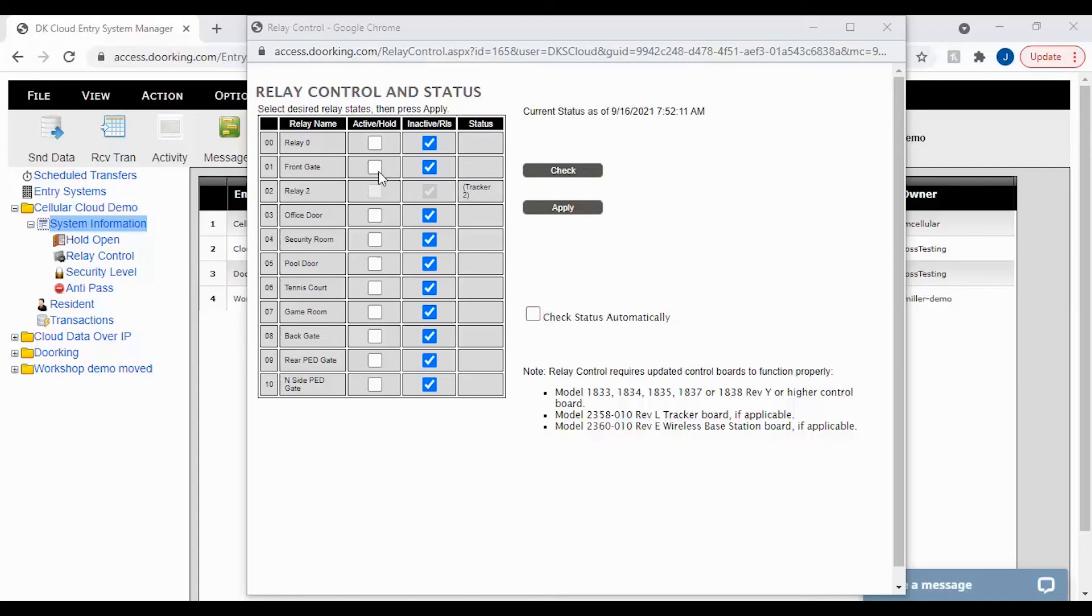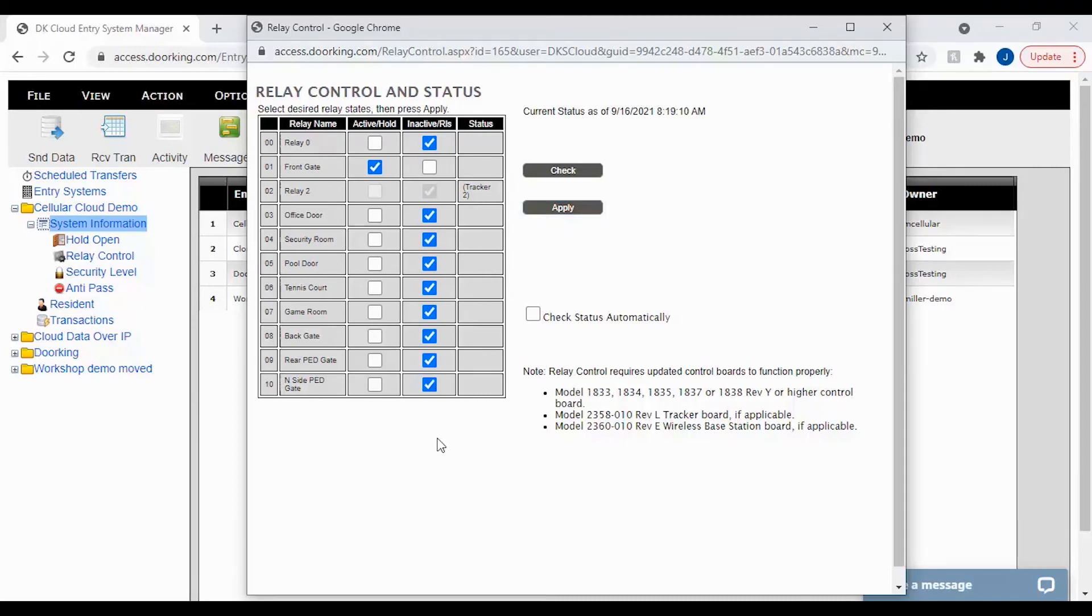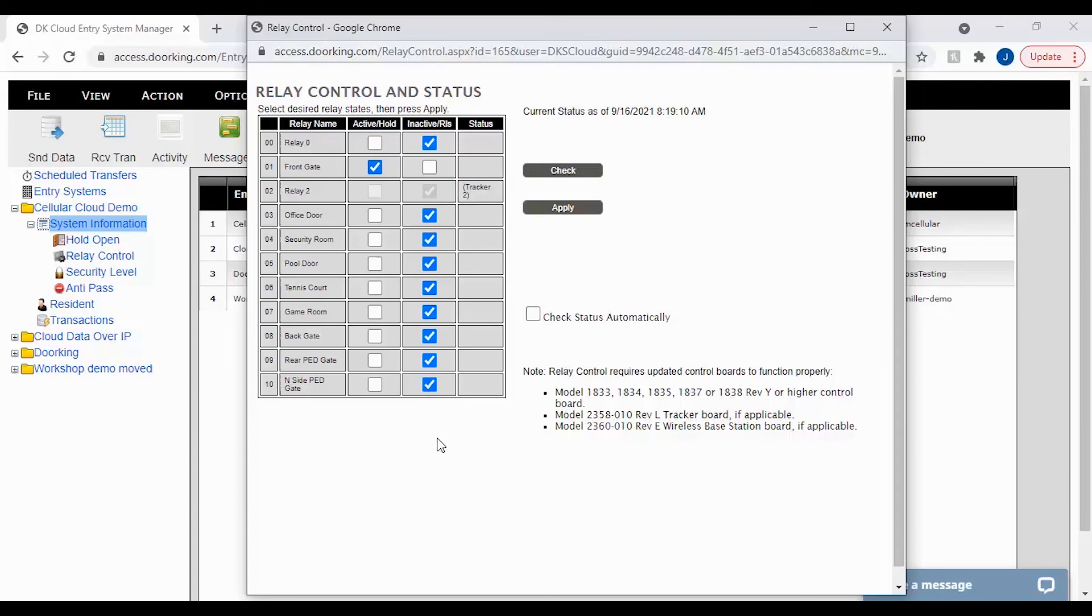To toggle a relay simply select the opposite action by checking the box and then click apply to push the change. Toggling relays if there is a hold schedule: If the relay is activated before the hold schedule begins, it will end with the schedule. If the relay is released before the hold schedule ends, it will activate automatically at its next scheduled time.